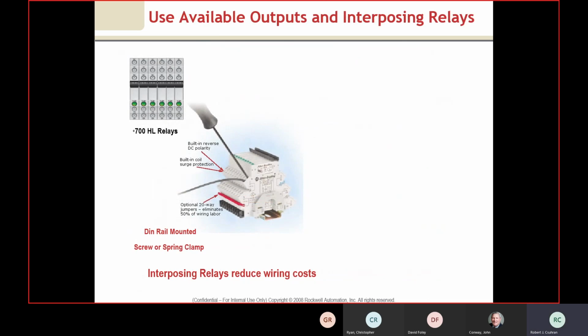So here is our 700 HL relay. Notice that these are mounted next to each other like a terminal block. They've got surge protection, DIN rail mounted. They come in screw clamp or spring clamp. So obviously, if you're not aware of these and it fits the 6 amp for single and 10 amp for the unit, if it meets the need, it's maybe an easier way to mount these without taking up a lot of panel space. And obviously the heat associated with a number of separate relays.